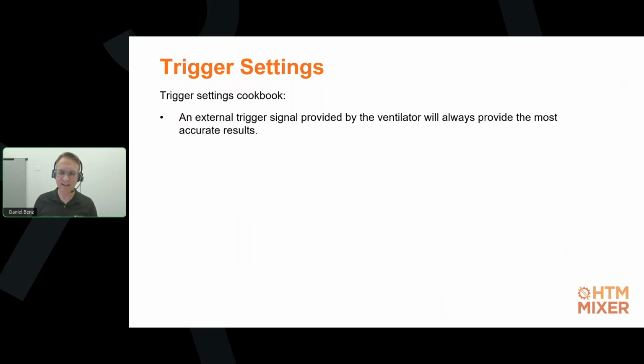The issue is that not many ventilators actually provide such a signal. Typically in the field, I've seen the Philips V60 and maybe one other, I can't remember which brand it was, but most of them don't. Additionally, a trigger cable is just an additional part in your setup, so it makes your setup more complex. Therefore, the more common way is to use the pressure or flow signal measured by your gas flow analyzer.